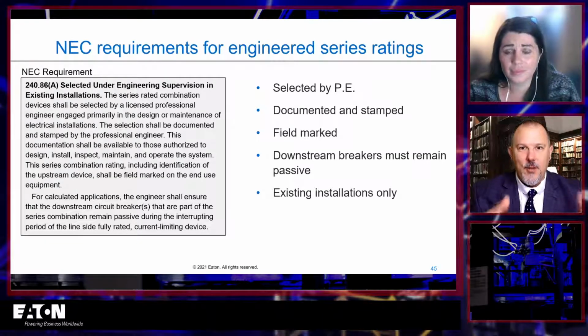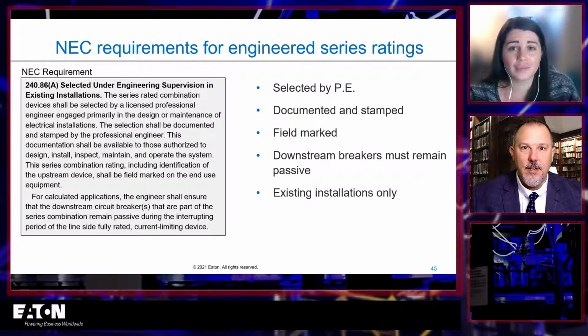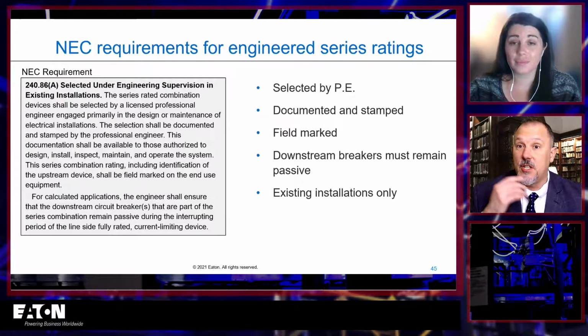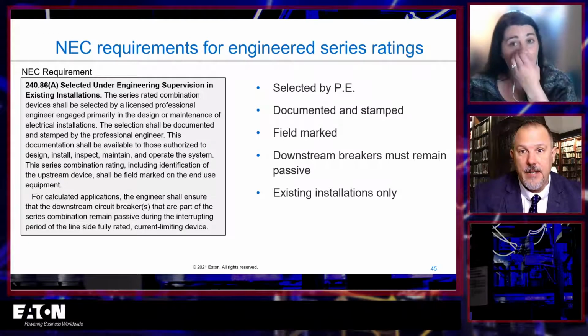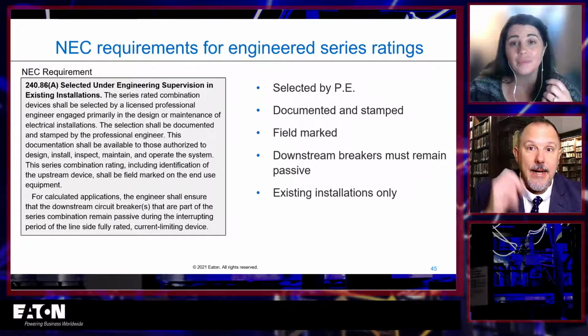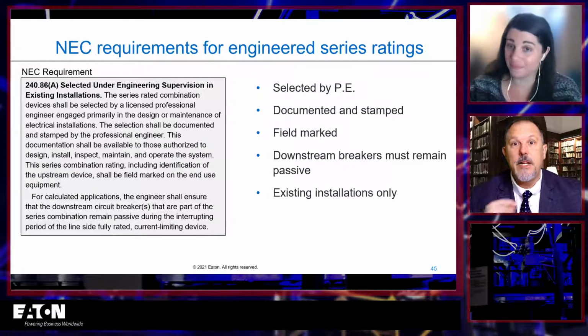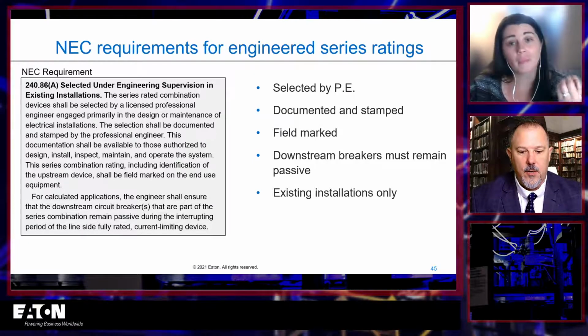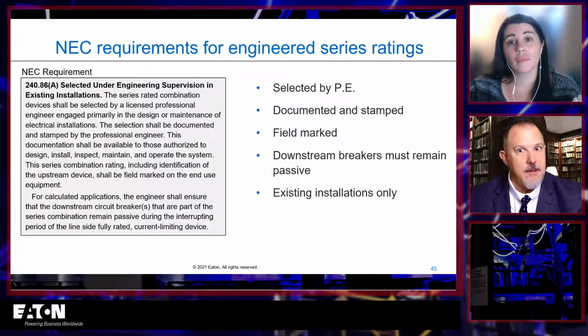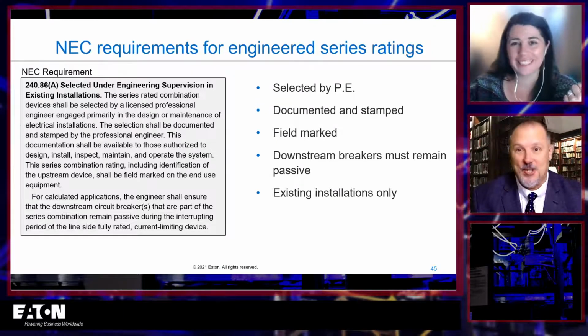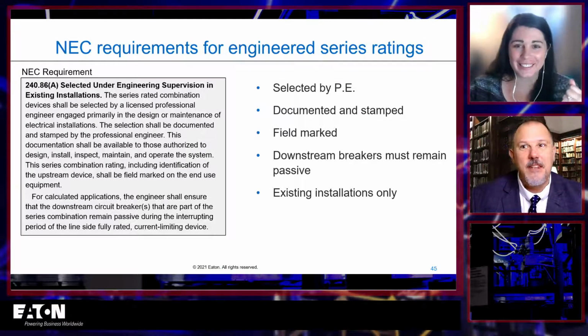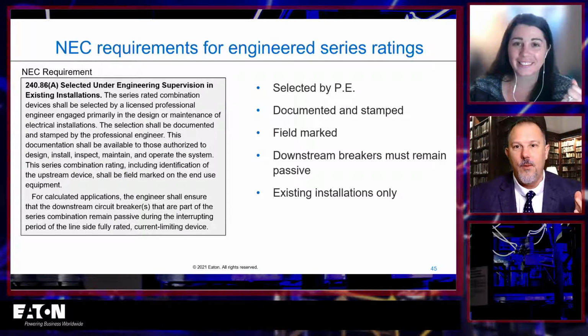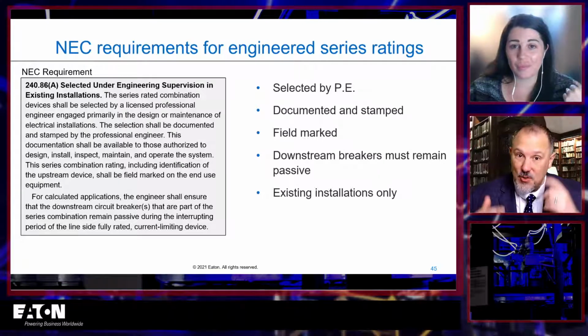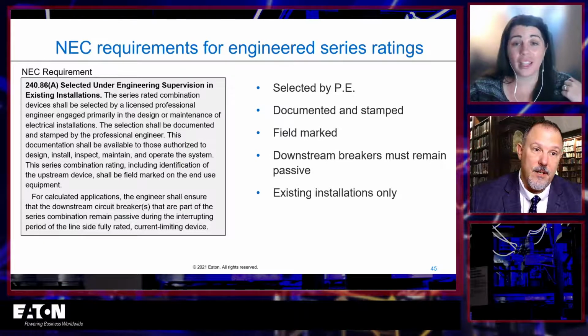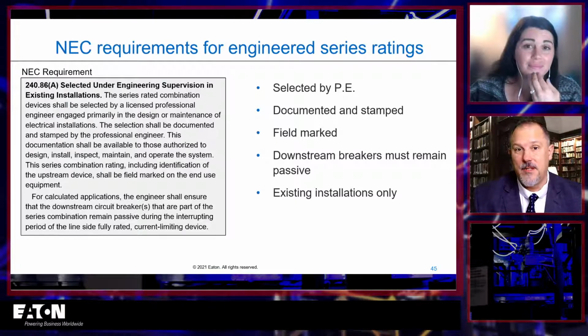And whenever you get into things like series ratings, you're going to have to cross your T's and dot your I's, because you make a mistake, a fault happens, you get that unintended rapid disassembly in the field. Somebody calls you and says this happened, and you say, well, I did this, and they say, well, we talked to the manufacturer, and they were out here and showed us that you made this mistake. Well, why did you go down that road to begin with? Because at the end of the day, I don't believe it's really all that much money. That's what it comes down to.